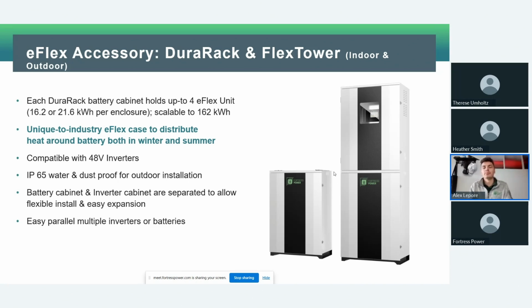The reason you may want the Durarack - I mentioned the eFlex Max is outdoor rated and has a built-in aluminum enclosure, and the eFlex Max has a built-in 300 amp bus bar, allowing you to bus batteries together directly on the battery. But for larger systems, or systems installed outside, the Durarack can act as another layer of protection for the battery from the elements.